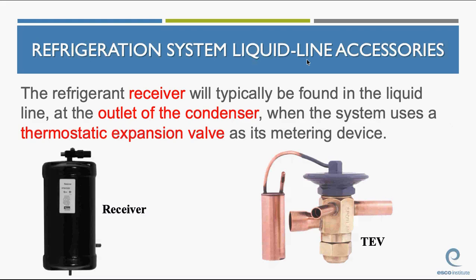The refrigerant receiver will typically be found in the liquid line at the outlet of the condenser when the system uses a TXV as its metering device. Again, in a lot of systems with TXVs, you have a receiver. The receiver holds a large amount of refrigerant. You can actually use the receiver sometimes to evacuate the refrigerant into.